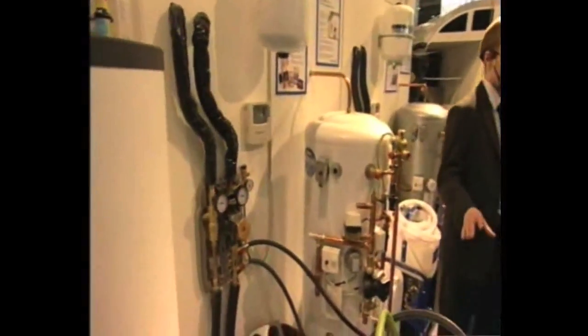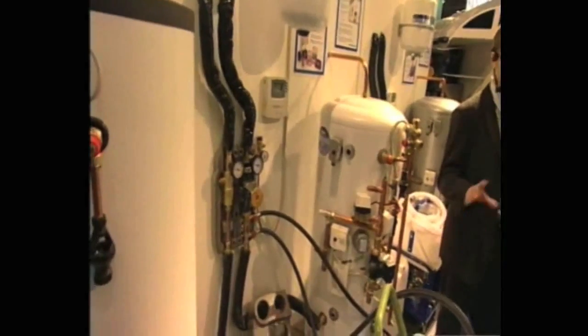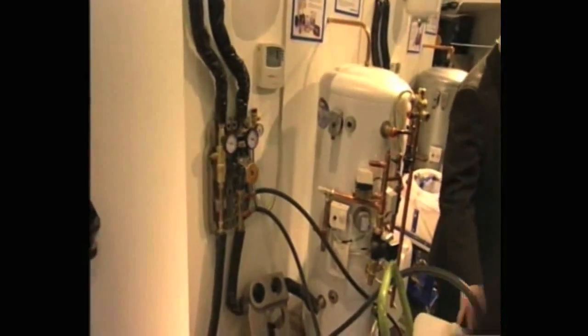And when you look inside the pump, you will see that there's some air coming out of there, and eventually that air will be dissipated through the pump, and all the air will be got out of the system. And how often are we talking about doing this? How regularly? Typically, whenever the system is filled and pressurized, that's the only time we really need to use this.